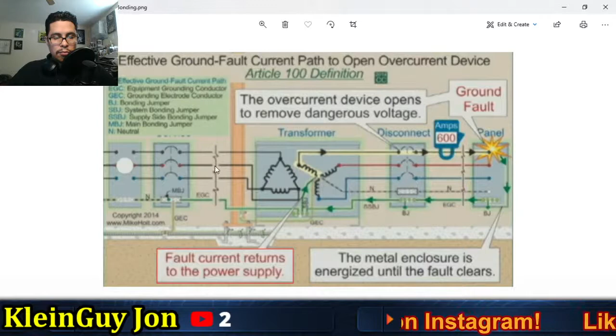You can even have this equipment grounding electrode conductor bonded to the steel from the transformer, and you'll still get parallel paths. You get all these paths, and it's going to the earth, and then you kill somebody. You create a voltage gradient. Someone's leaning on steel. Boom, they're done. That's it.